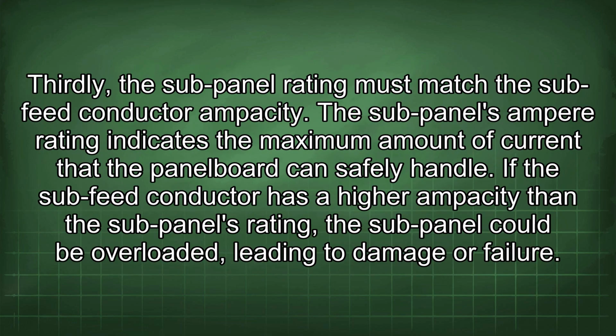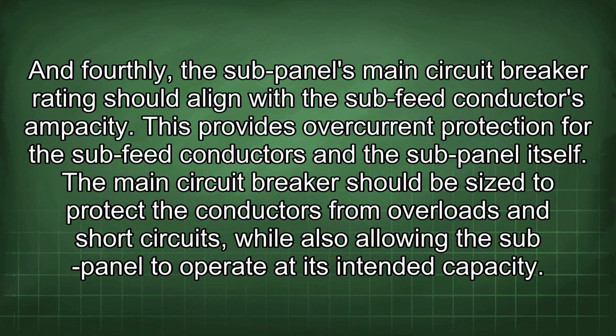Thirdly, the sub-panel rating must match the sub-feed conductor ampacity. The sub-panel's ampere rating indicates the maximum amount of current that the panel board can safely handle. If the sub-feed conductor has a higher ampacity than the sub-panel's rating, the sub-panel could be overloaded, leading to damage or failure. And fourthly, the sub-panel's main circuit breaker rating should align with the sub-feed conductor's ampacity. This provides overcurrent protection for the sub-feed conductors and the sub-panel itself.